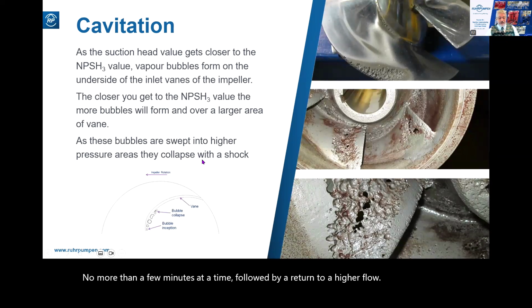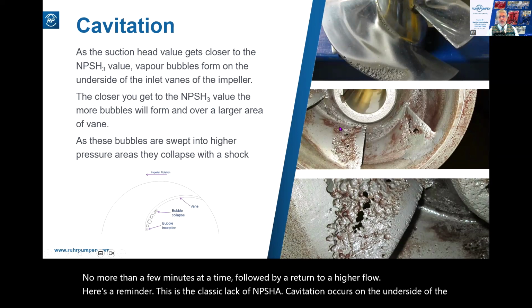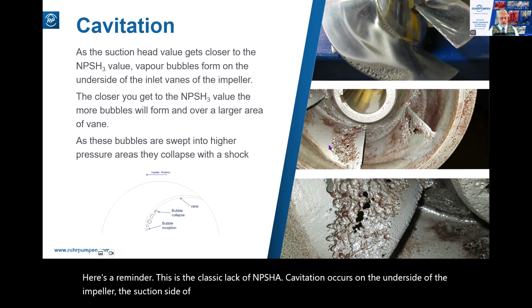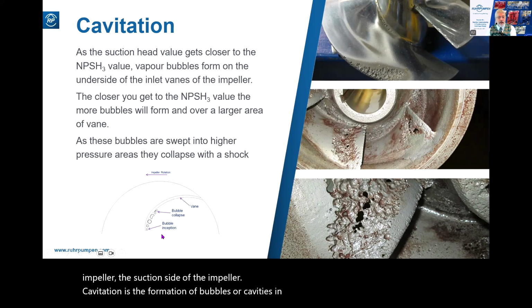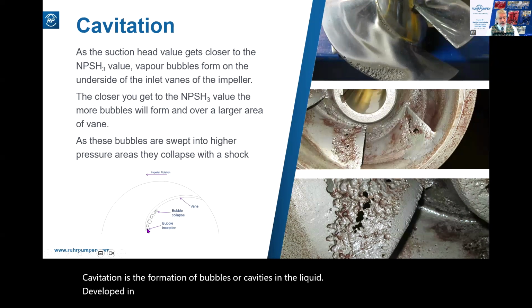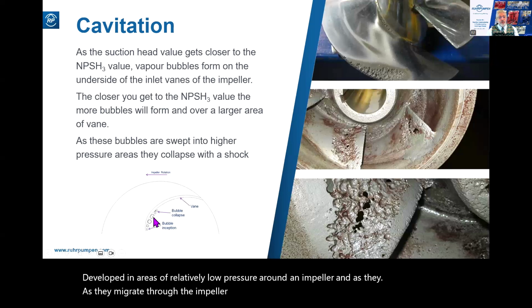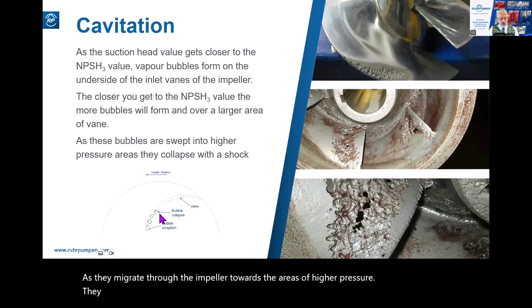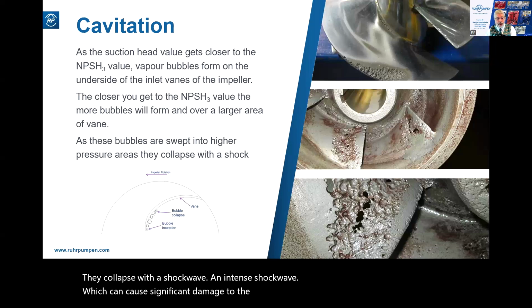Here's a reminder. This is the classic lack of NPSHA cavitation. Occurs on the underside of the impeller, the suction side of the impeller. Cavitation is the formation of bubbles or cavities in the liquid, developed in areas of relatively low pressure around an impeller, and as they migrate through the impeller towards the areas of higher pressure, they collapse with a shock wave, an intense shock wave, which can cause significant damage to the impeller and the pump housing.